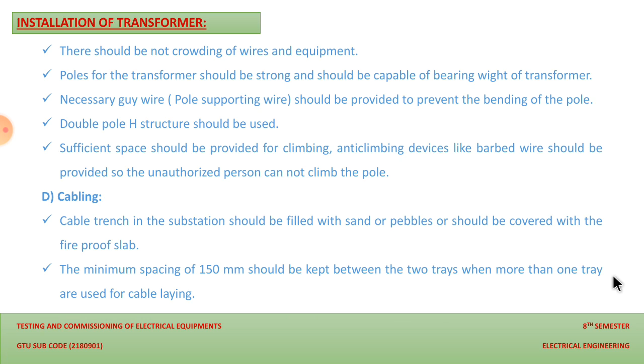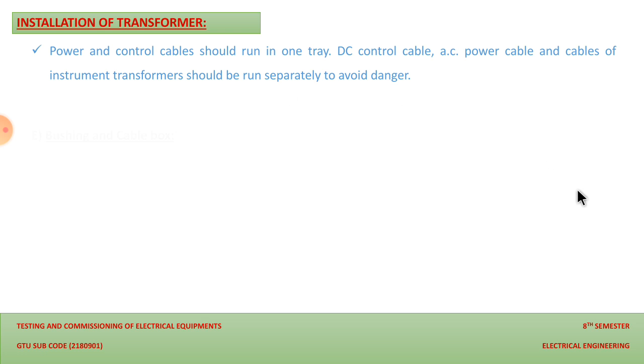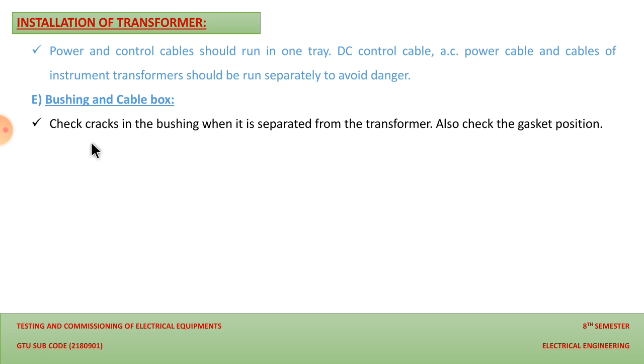Now the power and control cable should run in one tray, and DC cable, AC cable, and cables of the instrument transformer should be run separately. This is advisable to protect our transformer from harmonics. The next point is the bushing and cable box. So yes, check for cracks on the bushing when it is separated from the transformer. Also check the gasket position so that we can protect our transformer from flashover.